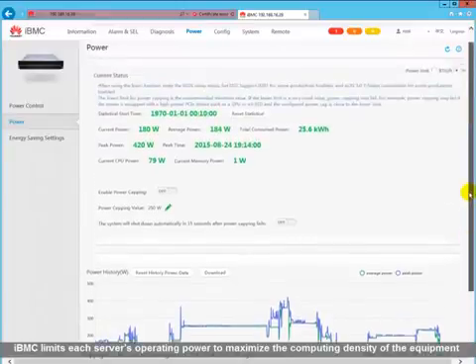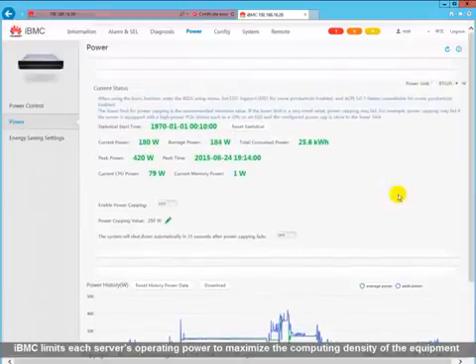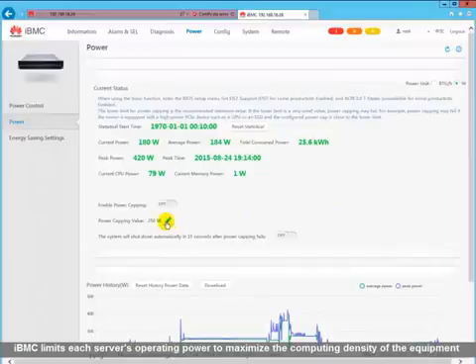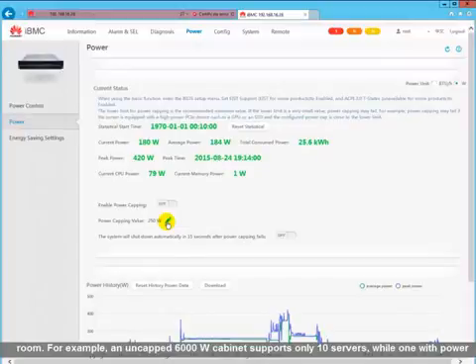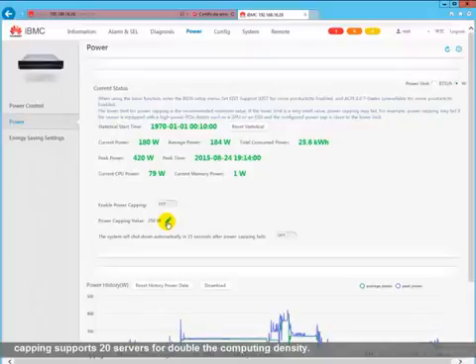IBMC limits each server's operating power to maximize the computing density of the equipment room. For example, an uncapped 6000-watt cabinet supports only 10 servers, while one with power capping supports 20 servers for double the computing density.